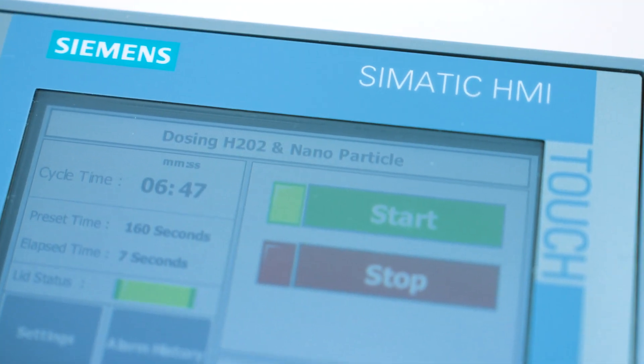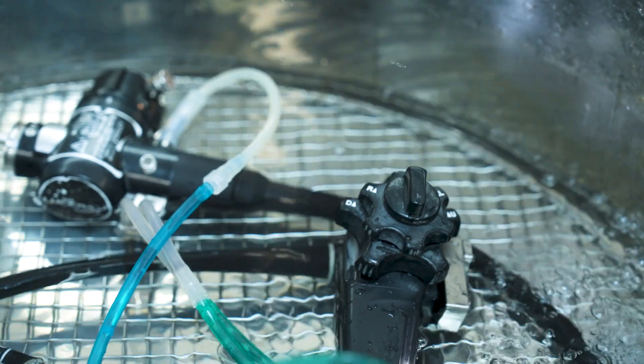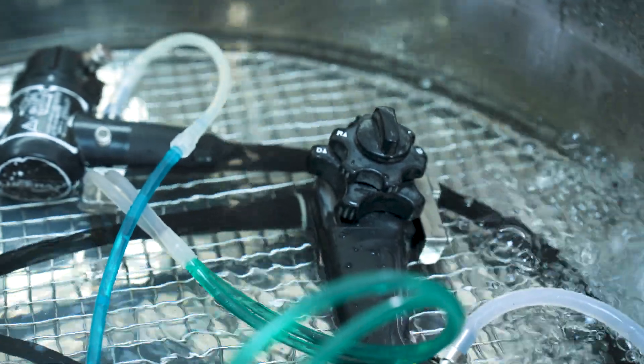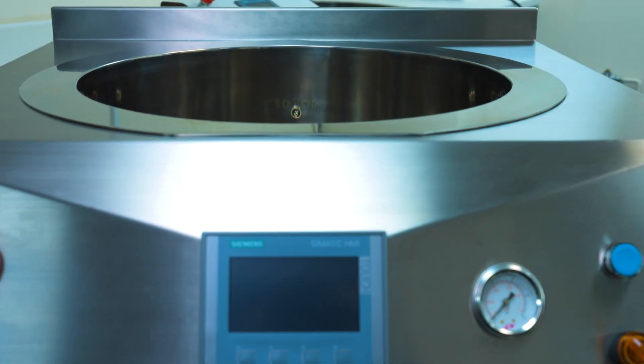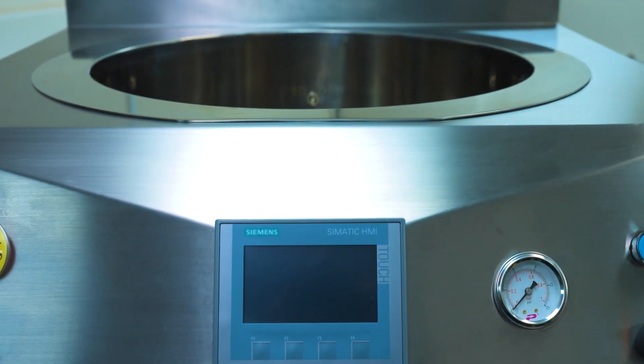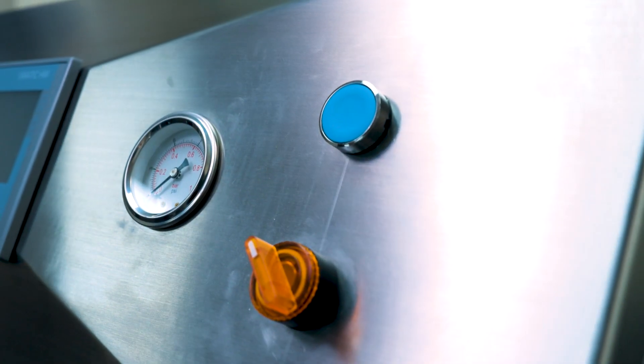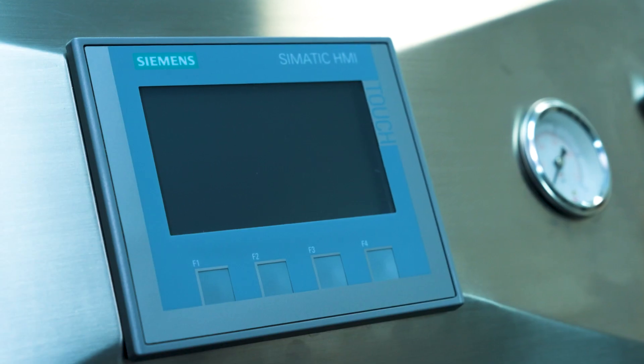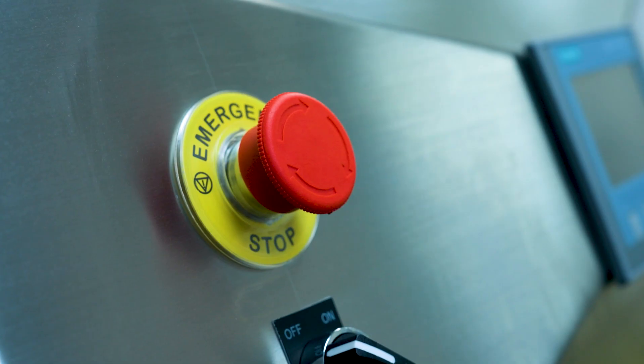On average, it costs £15 to manually clean an endoscope. We free-issue Kamsins and then charge £15 per clean of endoscope. Another advantage of the Kamsin is the elimination of extra PPE that causes clinical waste, such as sponges and brushes needed to manually clean the endoscope. Also, instead of needing two or three members of staff continually cleaning endoscopes, with a Kamsin you only need one member of staff to load and start the machine.